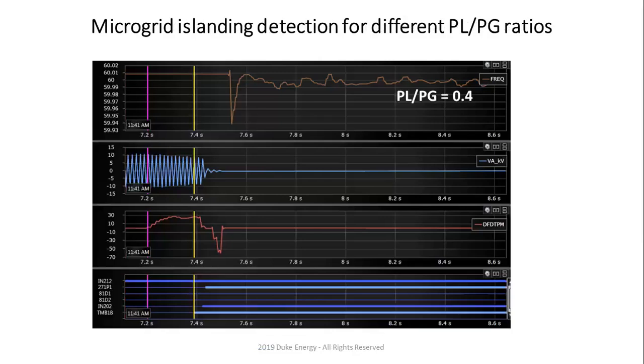So in order to do that, we have tested numerous things, right? And what you can see over here is response as recorded by the relay for PL over PG equal 0.4. On the top, you have frequency. Then you have a voltage on phase A. Then you have the rate of change of frequency, and then you have essentially what happens on the feeder, right? So input 212 on the bottom is when we actually initiate the islanding by pressing the button to open the islanding switch, not islanding switch, but the POI, point of interconnection.